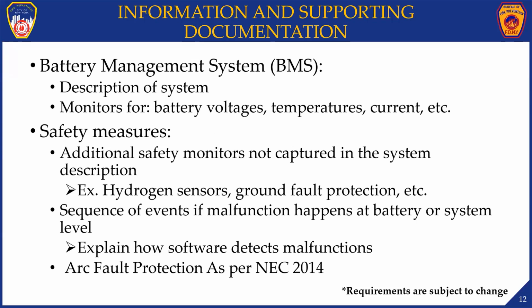As part of our rule, we require all ESS systems to have battery management systems. Since not all battery management systems are equivalent, we require a description of the BMS, what it monitors, who will be monitoring the output of the BMS, how the BMS can detect that a failure has occurred, the steps that are taken if failure is detected by the BMS, and also provide any information on any other safety measures that are included, like gas sensors, hydrogen sensors, thermal sensors, ground fault protection, arc fault protection.